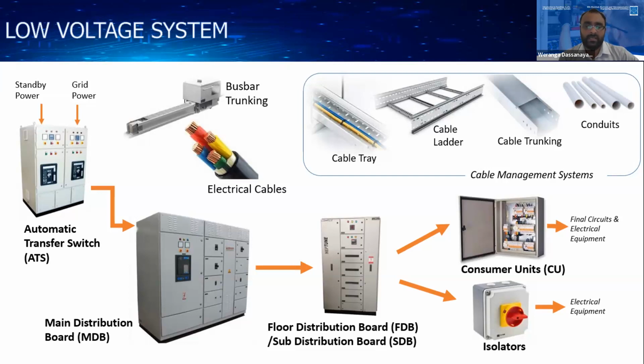small. When we are using multiple cables, we have to use very wide cable trays or cable ladders, like a very wide cable management system. But when we are using a bus trunking system, we can accommodate it in a very small space. So our transmission and distribution can be done in a very small space. So mainly you may see these types of power distribution arrangement when you go to a building. So you should identify how this power is distributed, from cables or from a bus bar trunking system.